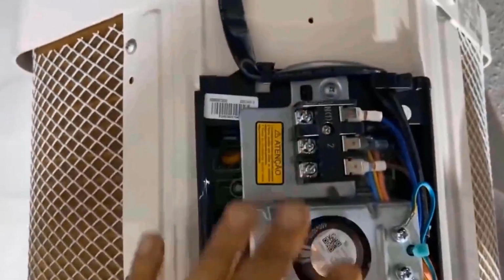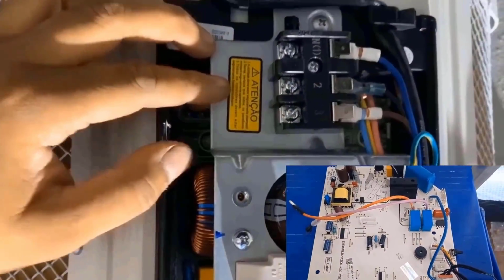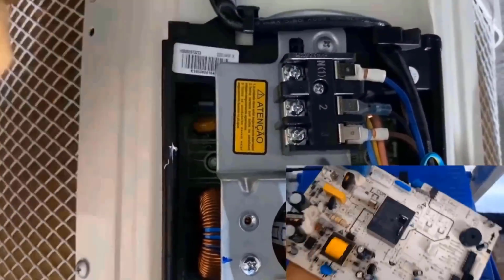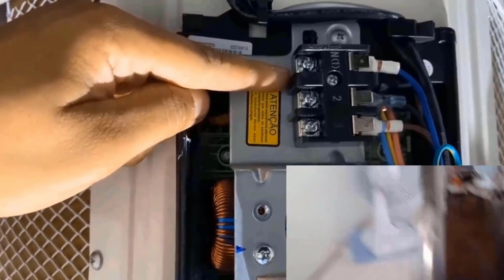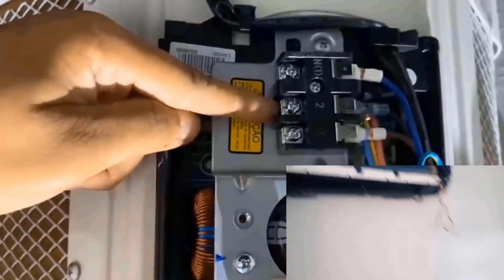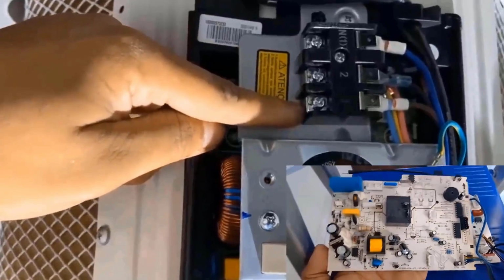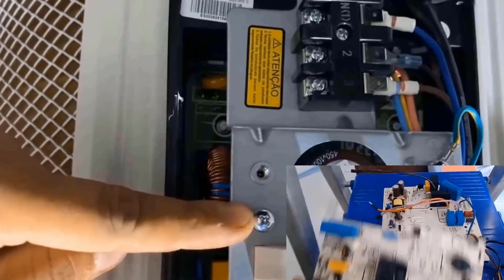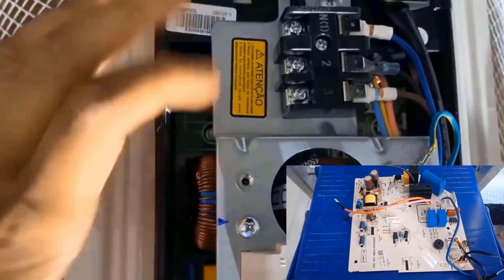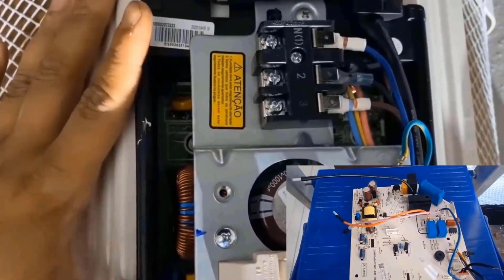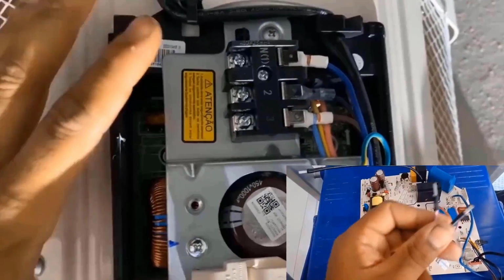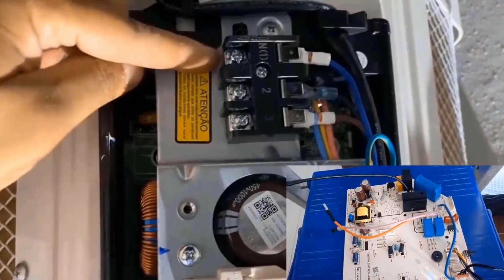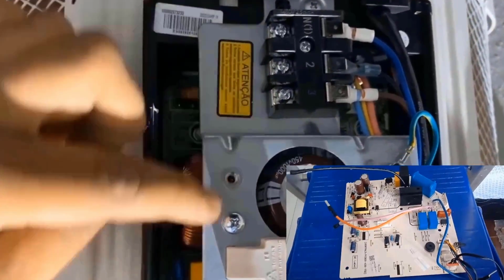In this case, it is important to check the condenser, remove the cover and check that everything is in order, that there are no oxidized or rusted wires, as this can prevent the electrical signal from passing through, generating the error. If everything is correct, with no signs of oxidation or rust, and there is still a failure in communication between the evaporator and the condenser, the fault is probably on the evaporator PCB.